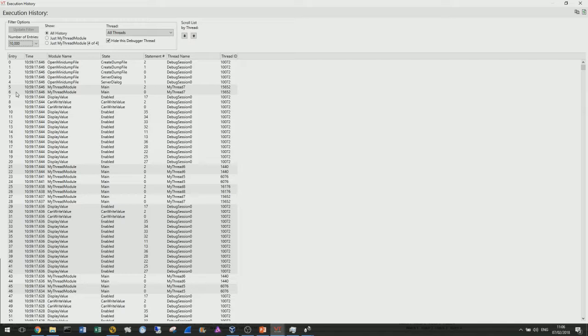Now, for those of you who have done the advanced course, the scripting courses, you'll know that we teach typically that you don't know the order in which we're going to execute statements because VTScada is entirely event-driven. And that is essentially true. But what you're peering into here is the actual ordered list of things, the way things happen. And at times, you do need to understand that. There is obviously a process execution.